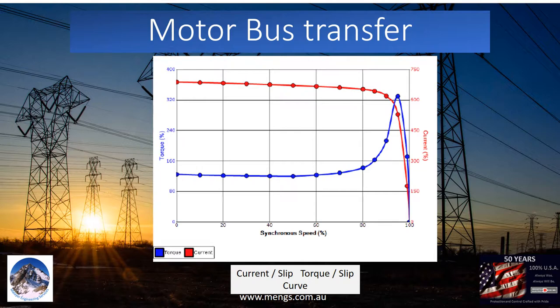As seen in the previous slide, motor speed will drop to lower than breakdown speed in about one second, depending on load and motor inertia. This means that in order to re-accelerate the motor after one second, we need to supply current close to lock rotor current. Lock rotor current in induction motors is about 5 to 8 times the full load current.